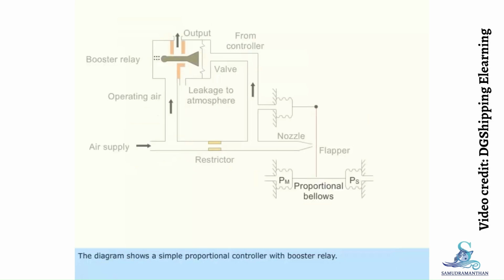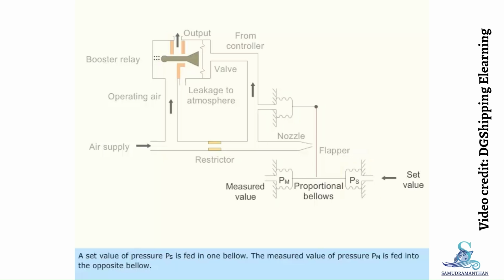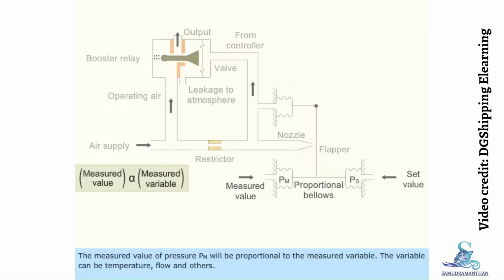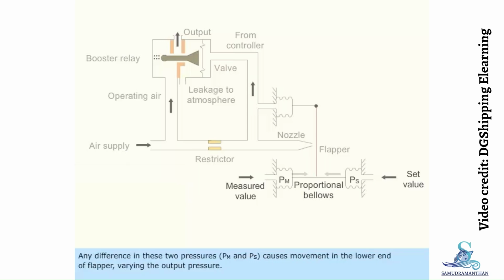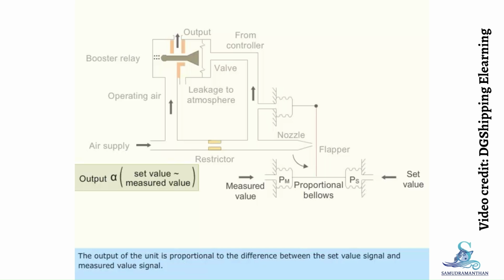The diagram shows a simple proportional controller with booster relay. A set value of pressure, P sub S, is fed in one bellow. The measured value of pressure, P sub M, is fed into the opposite bellow. The measured value of pressure, P sub M, will be proportional to the measured variable. The variable can be temperature, flow, and others. Any difference in these two pressures, P sub M and P sub S, causes movement in the lower end of the flapper, varying the output pressure. The output of the unit is proportional to the difference between the set value signal and measured value signal.